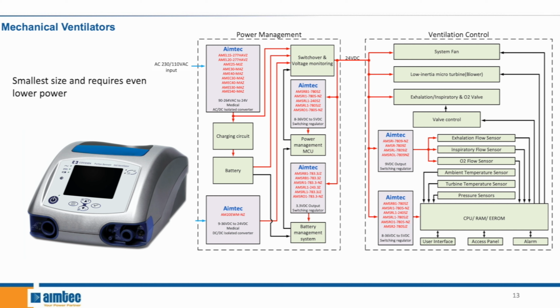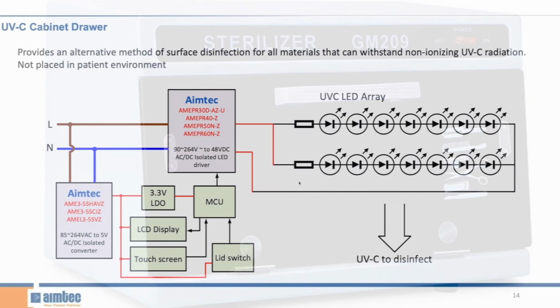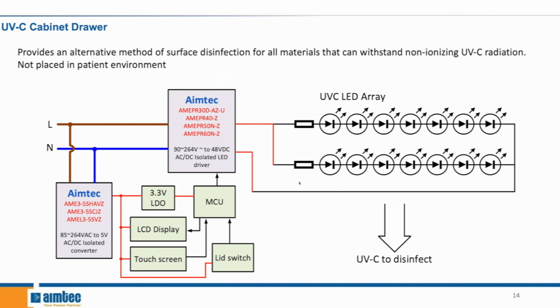Next, we have the UVC Cabinet Drawer. Most surface disinfection methods consist of using chemicals. The efficacy of these methods depends on the selected agent, manner of use, and the treatment time. Electronic devices such as phones and tablets can't be exposed to these strong chemicals as they can cause corrosion or damage the actual devices. That's why we use UVC rays to disinfect such devices. And in this case, we'll be looking at the UVC Cabinet Drawer, which is a small enclosure where you would put the device in it and it would disinfect it for you.